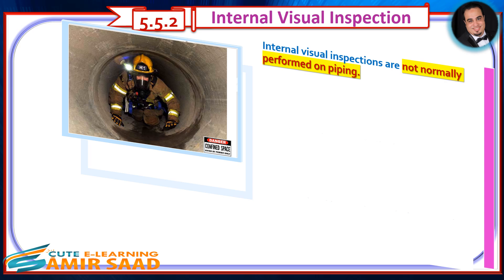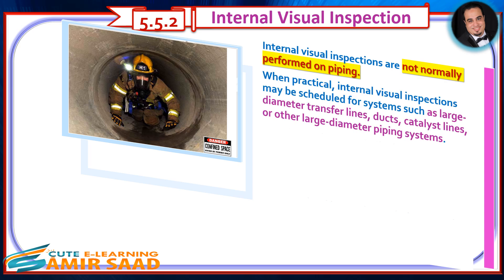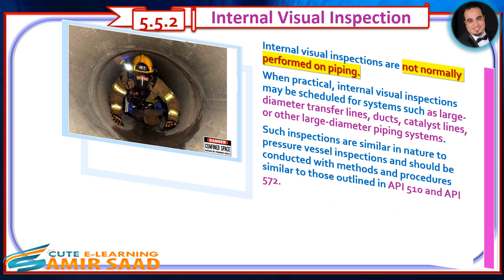Internal visual inspections are not normally performed on piping. When practical, internal visual inspections may be scheduled for systems such as large-diameter transfer lines, ducts, catalyst lines, or other large-diameter piping systems. Such inspections are similar in nature to pressure vessel inspections and should be conducted with methods and procedures similar to those outlined in API 510 and API 572.